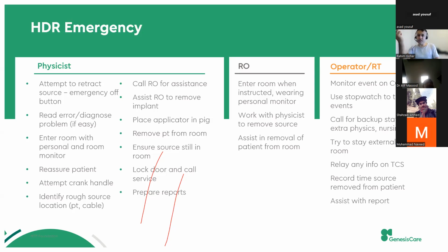So they can go a little bit deeper into how long a person can stay, and what the permissible limit is in case of an emergency. I really don't remember the figures, but they are mentioned in ICRP 103. The rule of thumb is if the source is 10 curie, you can spend less than a minute to get 1 millisievert. If the source activity is lower, then of course you can increase your time, but it's not good practice. It should be a minute or less.